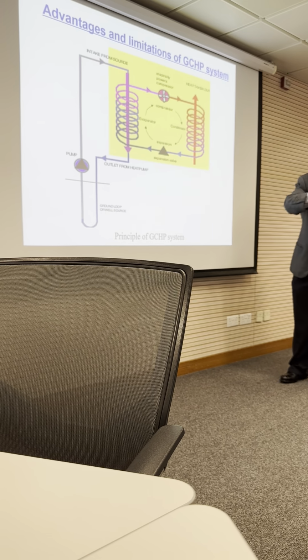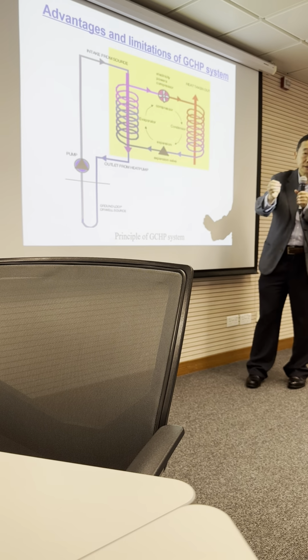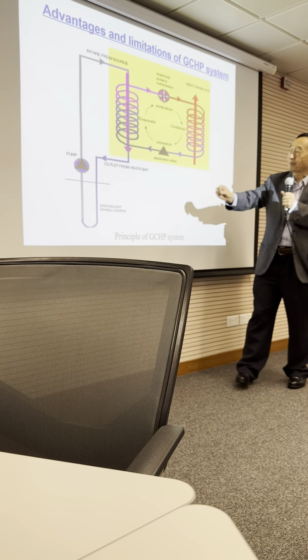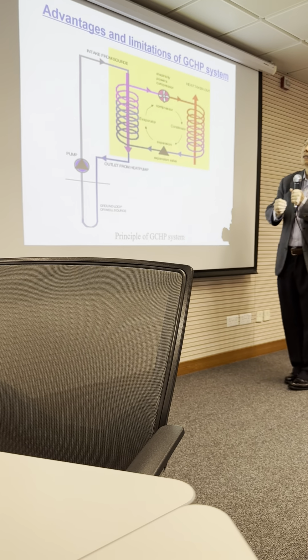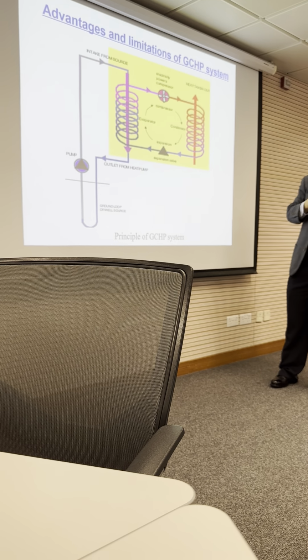Then the vapor is condensed into liquid, and then through the expansion valve, the pressure is lower, the temperature is lower, and then we have it passing through the evaporator. Then we need energy, because we produce energy here, so we need energy input. Then we use energy from underground. So we have another loop, an underground loop. We have a pump to take energy from underground to heat this evaporator, and then we have a cycle to produce hot water.